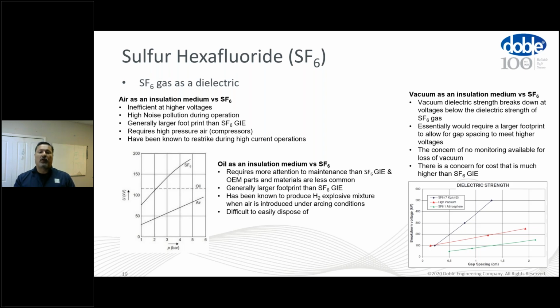Oil, of course, also requires more attention than SF6. A lot of these parts are less common now. It takes a very large footprint and has been known to produce hydrogen explosive mixtures when air is introduced under arcing conditions. And it's not as easy to dispose of, although there are different minerals and everything else, but still a difficult medium to deal with. Vacuum has been around for a long time, as you saw from my first graph of history. However, again, as the gap spacing increases and the voltage increases, SF6 maintains a very strong dielectric strength. If you were to use vacuum, you would need, again, a much larger footprint. You'd have no ability to watch that vacuum if there's a loss of vacuum. So there are some challenges there as well. So keep that in mind.